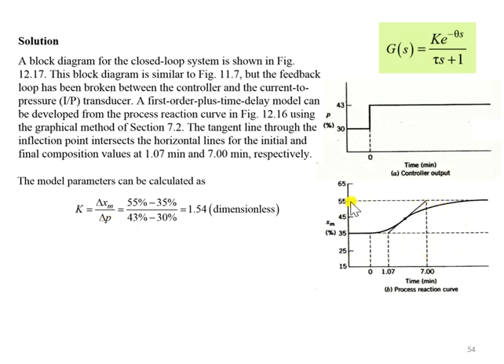...we can see the output changes from 35% up to 55%. This reaction is due to a step change from 30 to 43. By dividing those values, we can have the process gain K is equivalent to 1.54.